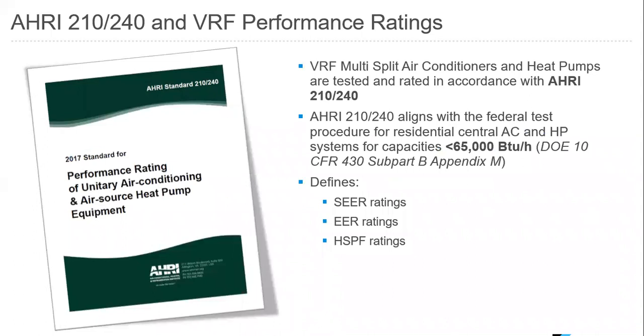So how are VRF and mini split systems rated? They're rated according to AHRI 210 and 240. AHRI 210/240 align the federal test procedures for residential AC equipment and heat pump systems for capacities less than 65,000 BTUs. This standard defines the SEER ratings, the EER ratings, and the heating ratings, HSPF ratings, for mini splits.